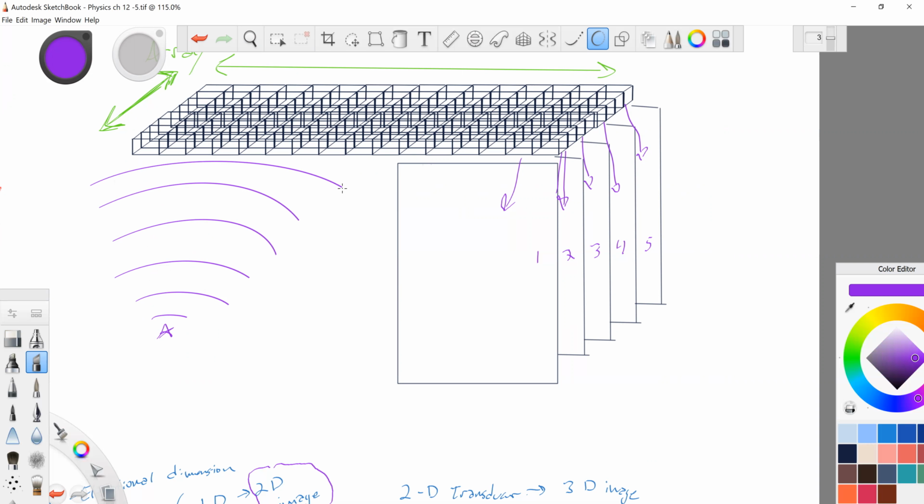A technique called, on page 194, dynamic aperture, can be used to make a sound beam narrow over a greater range of depths. It applies to the transmit hole and or the listening hole. I actually almost forgot, dynamic aperture works in both directions.